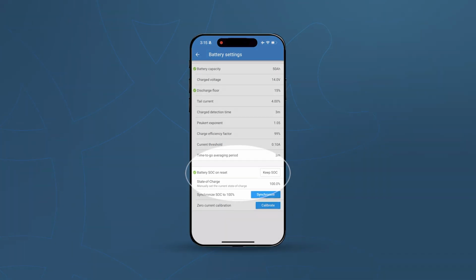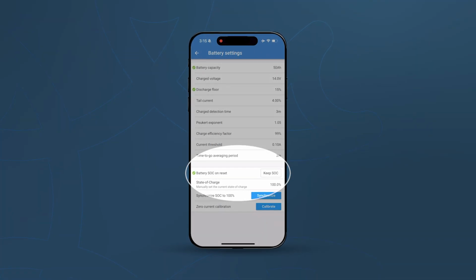For battery SOC on reset, I'm going to keep this as keep SOC. This means that if the battery was to disconnect, upon reconnecting, it would go back to the last known state of charge. If your battery does lose connection, I recommend putting it through a full charge cycle. It needs to go through this full charge cycle to recalibrate its state of charge.